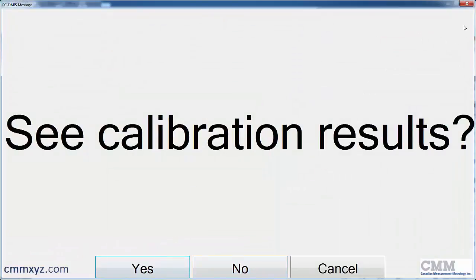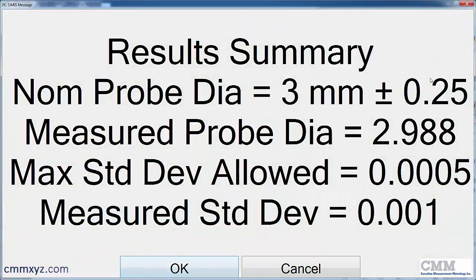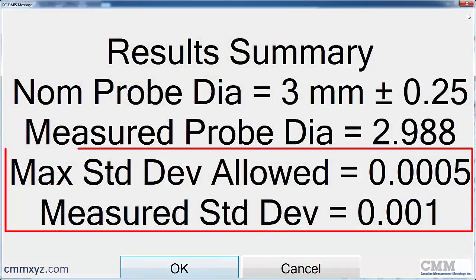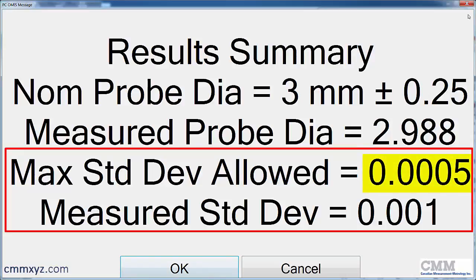Do I want to see the calibration results? Yes. So I'll say yes so we can review it. And with that open, you can see that the fail is in the standard deviation. So it's half a micron tolerance. And we've measured one micron. So that's a fail.